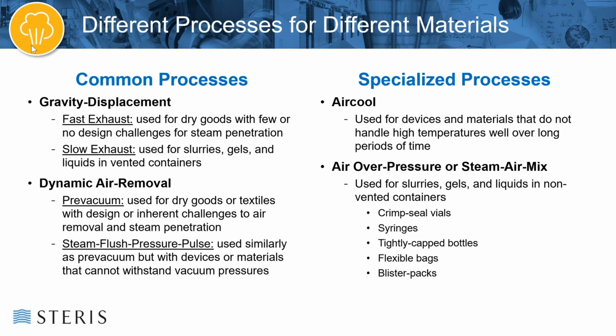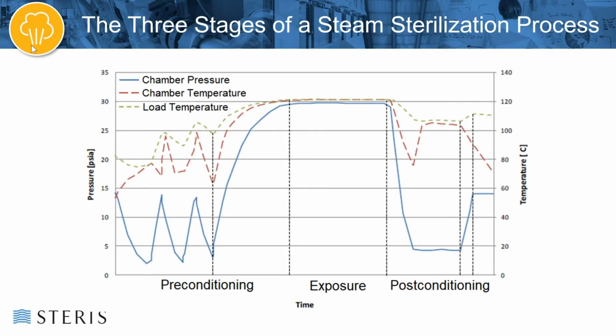Because when we are processing items in a steam sterilizer, there are some pretty dramatic pressure changes that take place at the front and at the end of the process. And these pressure changes, if not accounted for, will cause a non-vented container to rupture. So the air overpressure or the steam air mix processes are designed to mitigate that issue so that you can actually process these types of non-vented containers in a steam sterilizer.